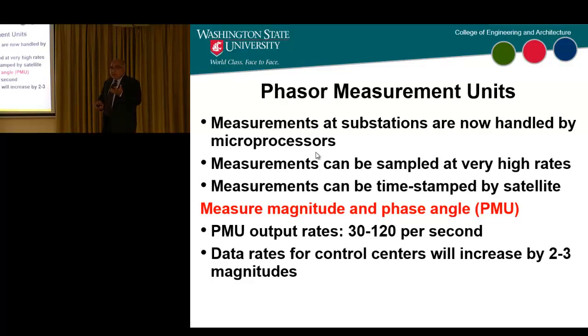Now, the big problem is that control centers were never designed for these high data rates. They're still designed for the 4-second, 10-second rates of data coming in. In fact, the funny thing is that many control centers are now tied to the substations with fiber optics, but they're still bringing in data at 4 seconds because that's what the SCADA software does.